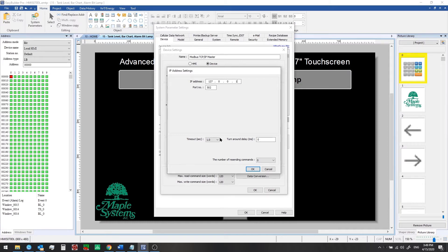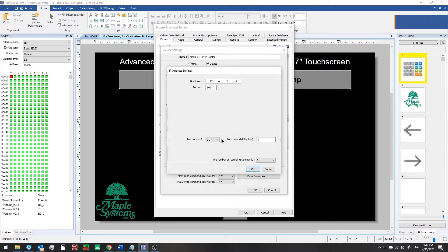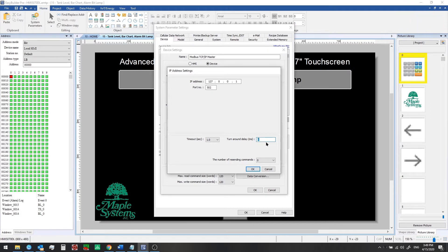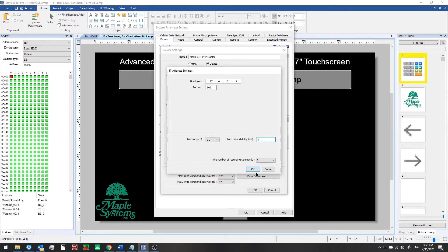There's a couple other settings here that you might want to be aware of. The timeout - timeout is how long the HMI will wait before it assumes the connection to your Modbus device has been lost. At that time it will show you a warning: device no response. Turnaround delay is an optional parameter. If you set this to some value like 5 milliseconds, then the HMI will wait an additional 5 milliseconds between each polling request to the Modbus device. Generally we can leave these as the default values.